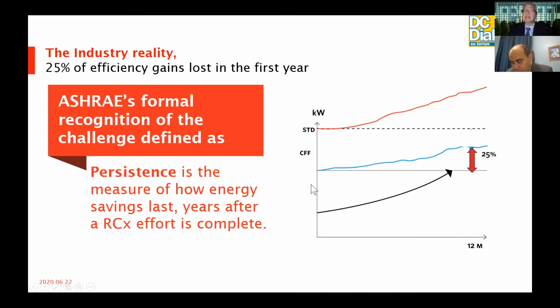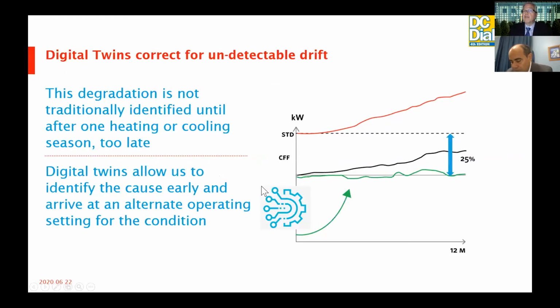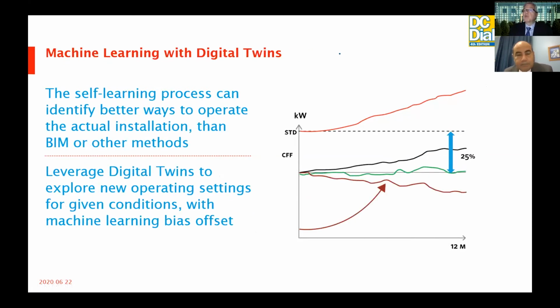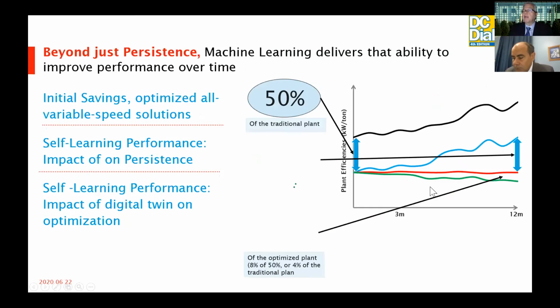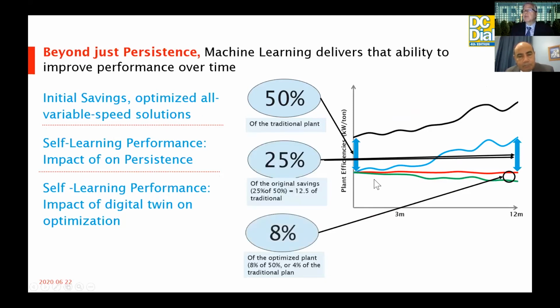ASHRAE has recognized that high performance systems tend to lose about 20% to 25% of their performance due to this drift. The digital twins allow us to move along this green line. And what we've seen is digital twins also help improve beyond what the predicted performance was originally, because they're learning over time new ways of operating the plant rather than the traditional approach that we've used for control. And this leads to an additional 8% of savings in terms of energy.